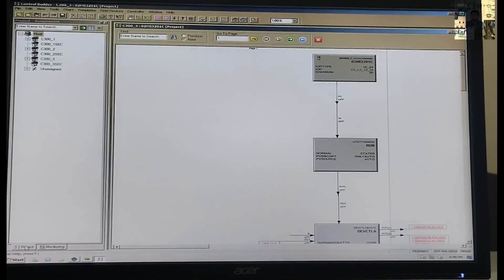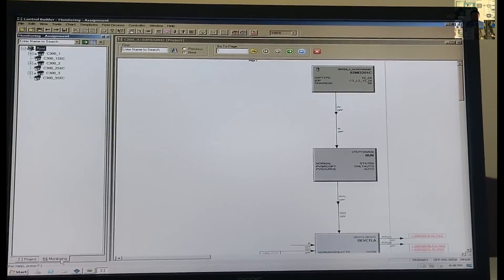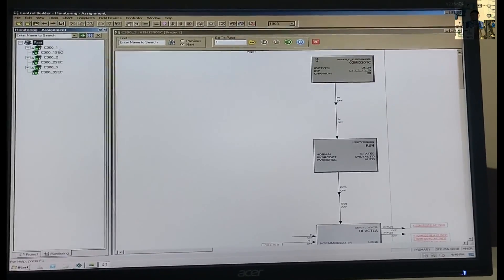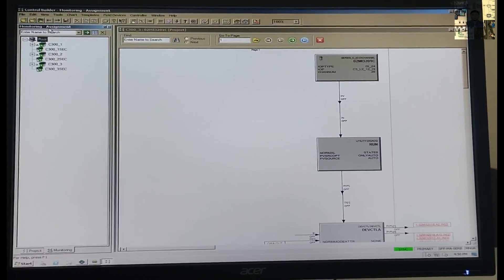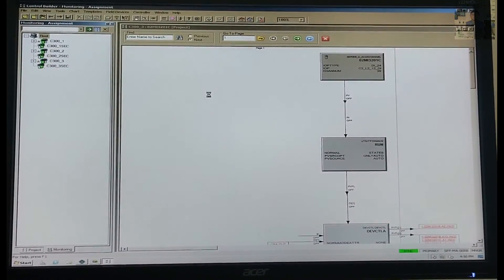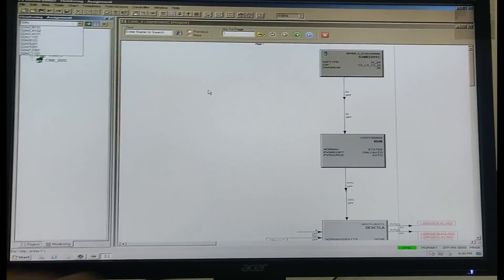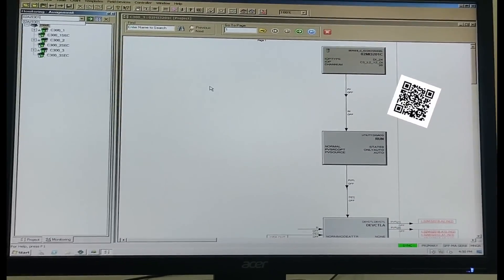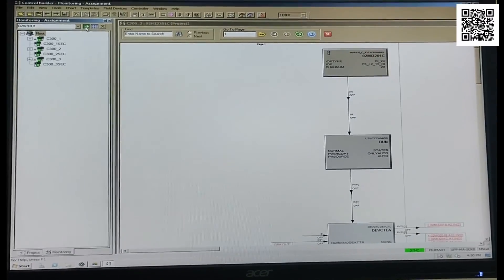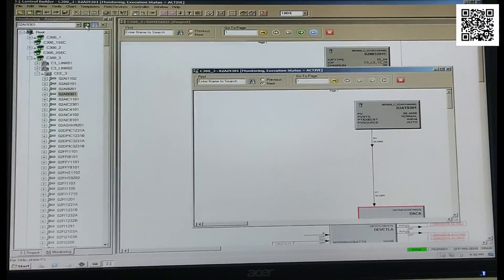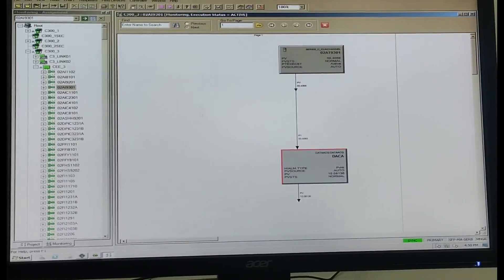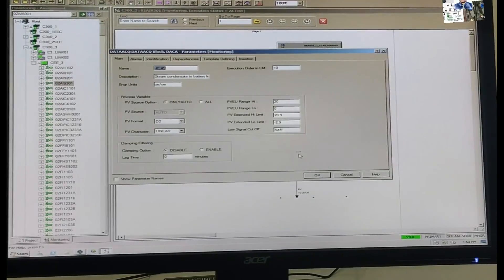There are two types of modes: Project mode and Monitor mode. In the project mode, we do the reconfiguration, and in the monitoring mode, we can see the status of the same program. So, we search for the desired tag that we want to reconfigure, put the tag number, and go to the play button. Here you can see the details of the same tag.